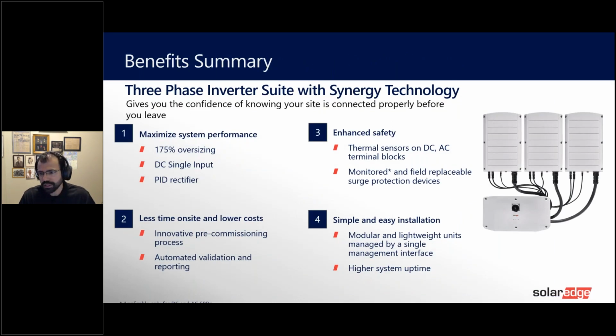And just one thing here, this is our Synergy platform, the Synergy inverter. That's for the larger applications, for large rooftop applications. We have all the benefits besides pre-commissioning, surge protector devices, monitoring of terminal blocks from a temperature perspective. I want to highlight the single DC input functionality, which we presented in the spring for Krannich here. It is a single DC input that allows savings on balance of system, and that's something Jacob is going to be introducing and explaining, the fact that we can put everything close together at a centralized location.